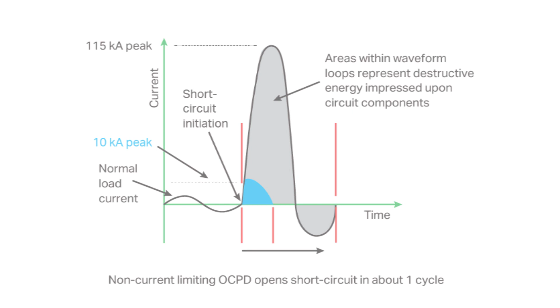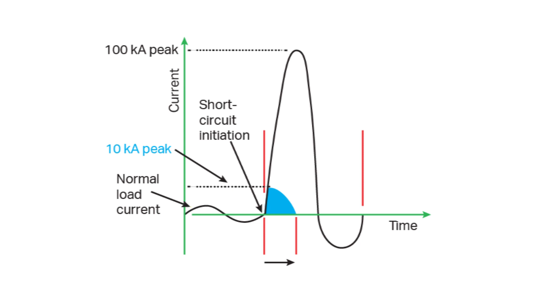In the first major fault current cycle depicted by the waveform, a non-current limiting overcurrent protective device would let through approximately 100 times as much destructive energy as a current limiting fuse. This is assuming an asymmetrical peak current of 100,000 amps and a peak let-through current of 10,000 amps. Modern fuse designs are current limiting and greatly reduce a fault current's destructive peak and duration to protect downstream equipment. This can reduce the bracing needs for bus structures and minimize the need for components to have high short circuit current ratings or withstand ratings.